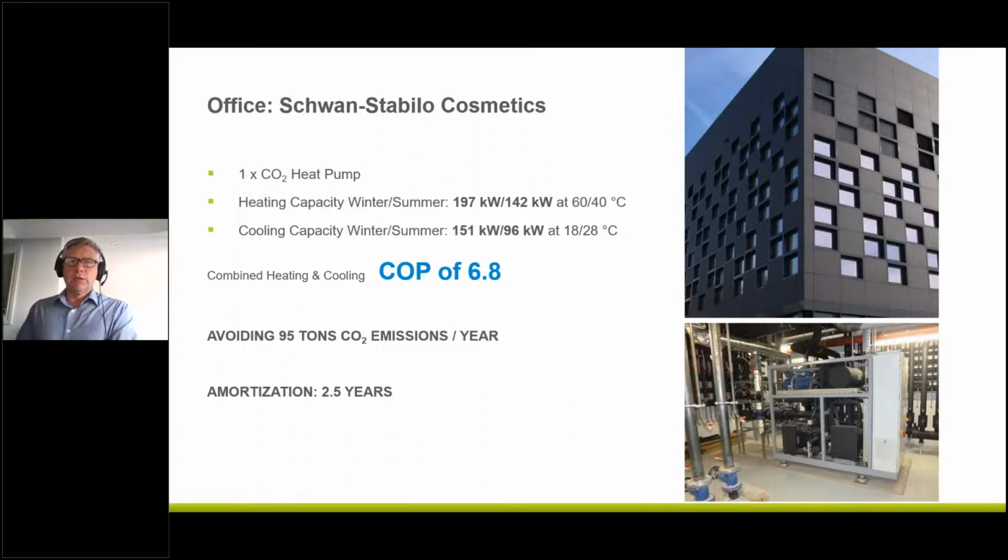So the various different loadings as well. Obviously, in winter, you're going to have higher heating requirements, and then vice versa in the summer. Okay, so an overall COP of 6.8, and it avoids 95 tons of CO2 per annum, and a payback of 2.5 years. There's a picture of the heat pump itself, quite a compact unit.